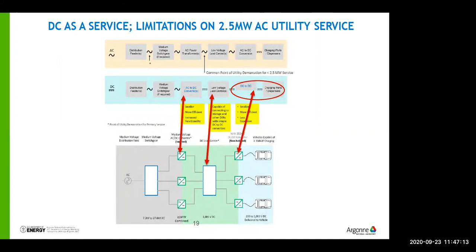That's the concept of DC as a service. The idea is that the utility owns all of this, that's important. This diagram shows the same thing but more hardware-focused. In the middle you see transmission and distribution, that's normally where your primary meter is, the first M just left of center. Then the medium voltage breaker, that always has to be there as your safety device, and then the solid state transformer.